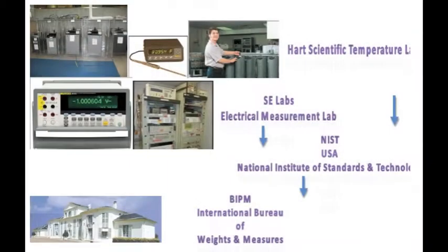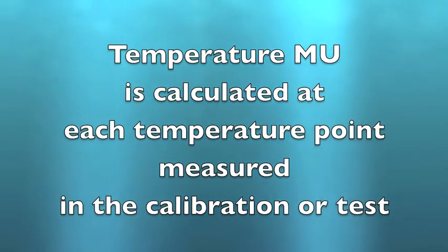The traceability chain goes: baths to Hart Scientific, meter to SE Labs, SE Labs and Hart to NIST, and NIST to BIPM. The temperature measurement uncertainty is calculated at each temperature point measured in the calibration or the test.